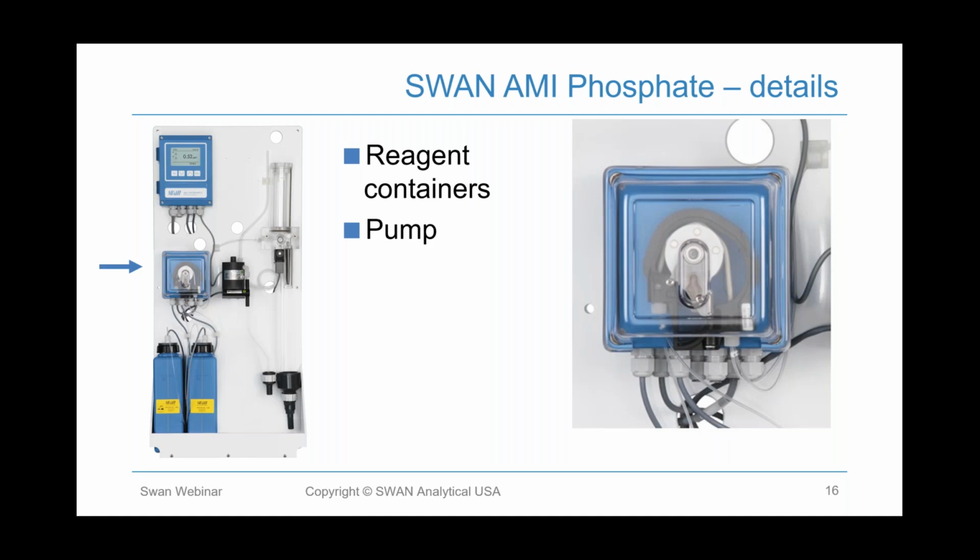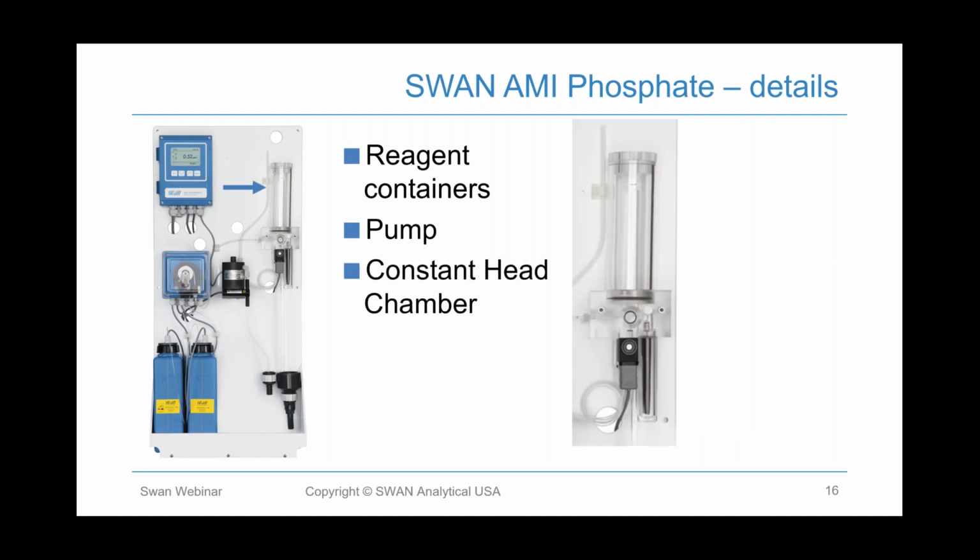This is a very simple, very robust pump, and we'll look at those clips there in a minute as to how those get changed. This is the constant head chamber, so we bring the sample into this head chamber and use it to fill the instrument.